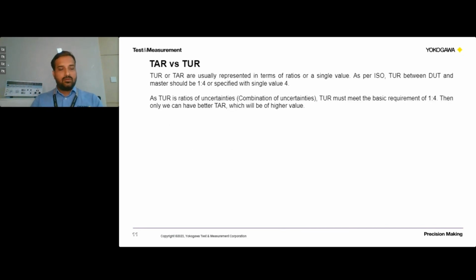Further we will discuss how TUR and TAR both are relevant in calibration labs, how these are different, and how these ratios are used to make decisions in the calibration labs. TUR or TAR are usually represented in terms of ratios as per ISO. TUR between DUT and master should be 1:4. That means the ratio between the uncertainty of the DUT and the uncertainty of the master should be 1:4. That means the uncertainty of the master should be 4 times better than that of the DUT.